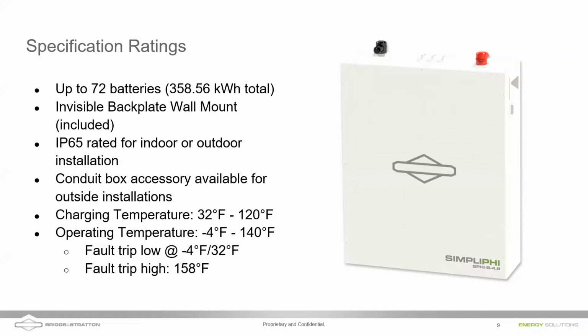Now, with being outside comes some temperature difficulties. On the high end, this battery can be operated as high as 140 Fahrenheit, and that means really being stored or discharged at up to 140 Fahrenheit. And it can also be charged as high as 120 degrees. So that's really quite high. You're rarely, if ever, going to see any issues charging on the high side. The issue really comes into play on the low side. So we do see plenty of environments that our batteries get installed in reaching 32 degrees Fahrenheit a few times throughout the winter.